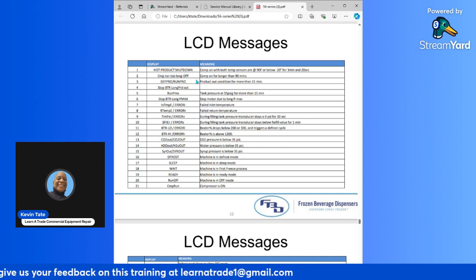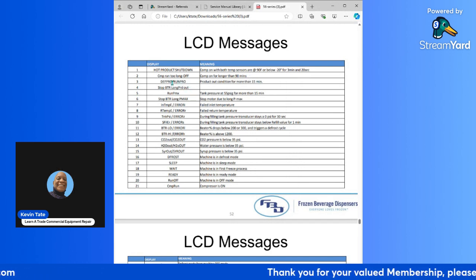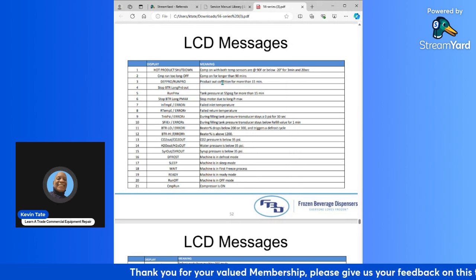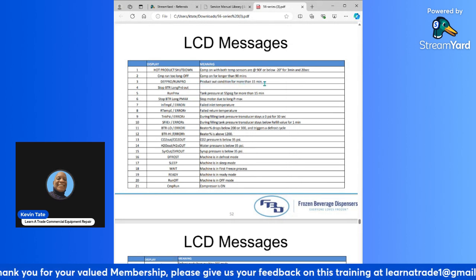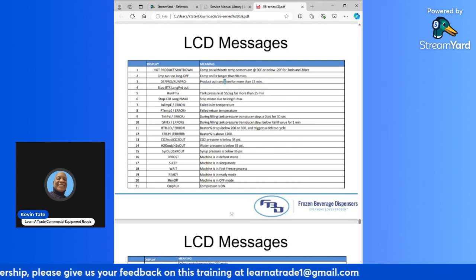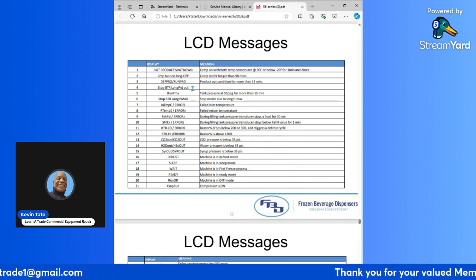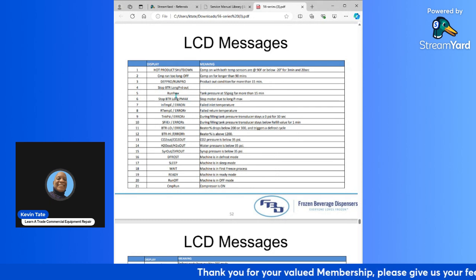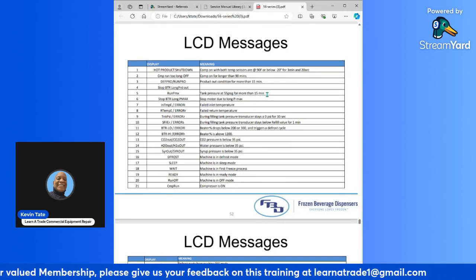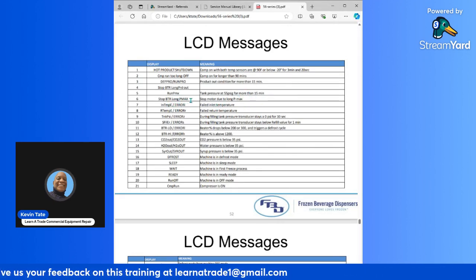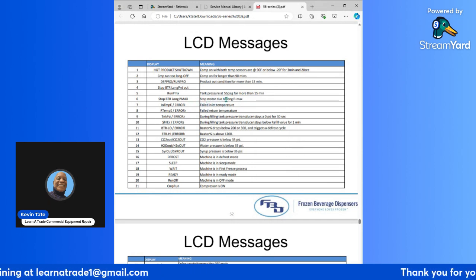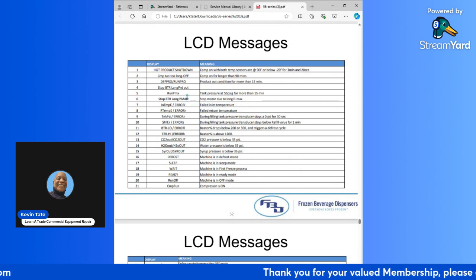Next is compressor ran too long. Compressor on for longer than 90 minutes. Defrost Pro / Run Pro, product out condition for more than 15 minutes. So if the unit runs without any product connected for longer than 15 minutes, this message will come up. Stop beater, long product out. There's no meaning for that. The run Pmax, that's your tank pressure at 55 psi for more than 15 minutes. Your stop beater, long Pmax, stop motor due to long Pmax. So the motor stopped because this Pmax error was up.